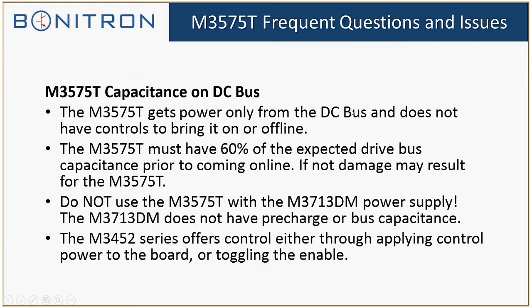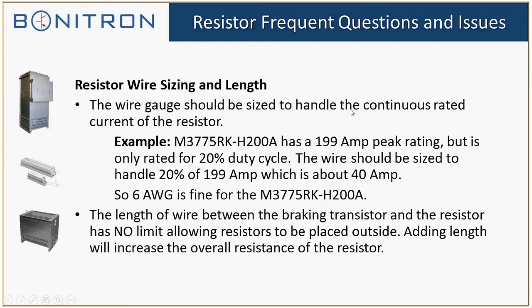Okay, so moving on to the actual braking resistor. There are a lot of questions about the braking resistors that I get, just in terms of troubleshooting and installation. The braking resistor, a lot of customers, once they see that it can handle 200 amps, they want to size the wire to handle 200 amps, full time. And basically I have to convince them that no, you don't really have to do that. Also, the terminals on most of our smaller resistors won't even be able to handle that.